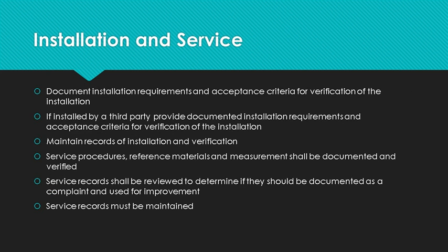All right, we're almost through with production and service provision. All we have left is installation and service. These are other sections that are frequently considered as not applicable. However, if you have a helpline, that is considered a service operation. Both installation and service activities must be documented with procedures explaining how to install the device and how to determine if it is functioning properly.